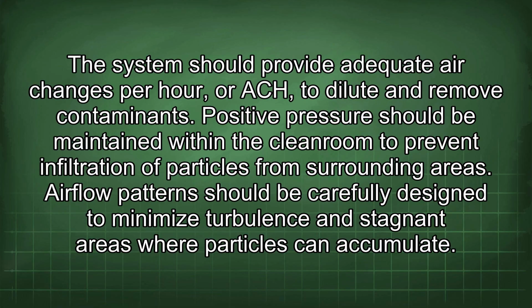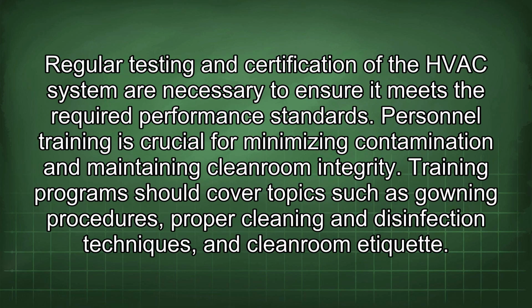Positive pressure should be maintained within the cleanroom to prevent infiltration of particles from surrounding areas. Airflow patterns should be carefully designed to minimize turbulence and stagnant areas where particles can accumulate. Regular testing and certification of the HVAC system are necessary to ensure it meets the required performance standards.